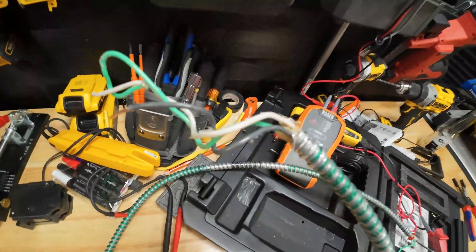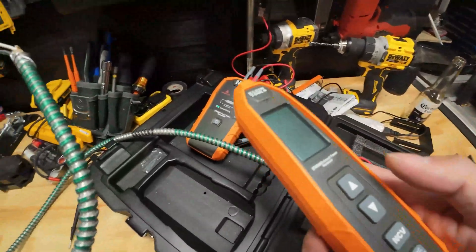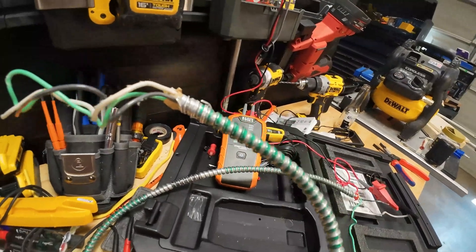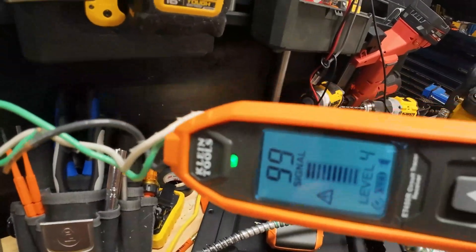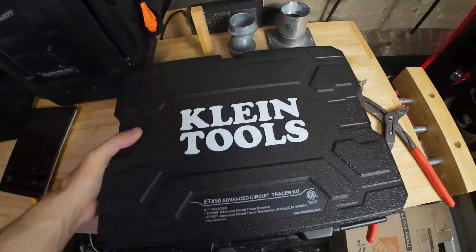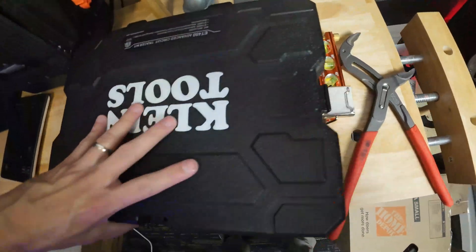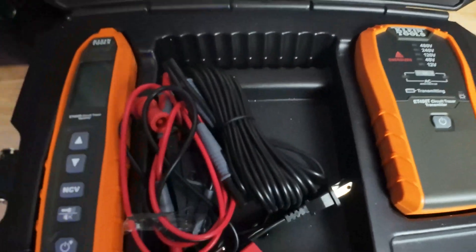73 on the exact wire we're trying to trace is not a good look. All the electrician channels on YouTube hook up the hot and neutral and seem to trace just fine — why is this method better? We're going to bump those numbers up off camera. This is the Klein Tools ET450, the advanced circuit tracer. If you use this as a circuit tracer it's similar to others, but if you use it as a toner, you're pretty much cheating — this thing is a cheat code.